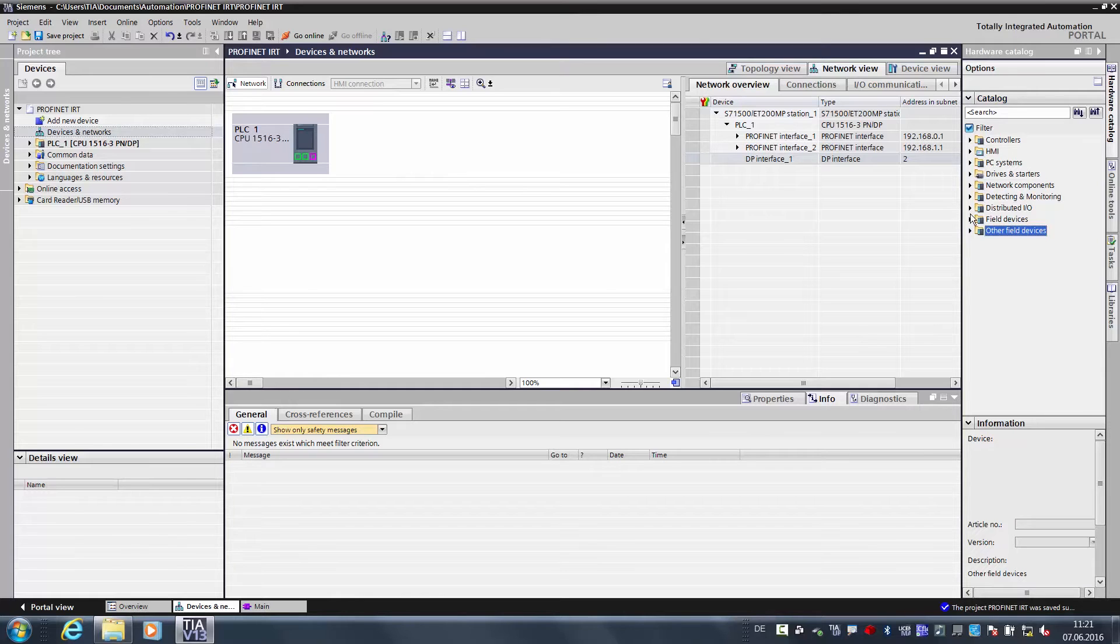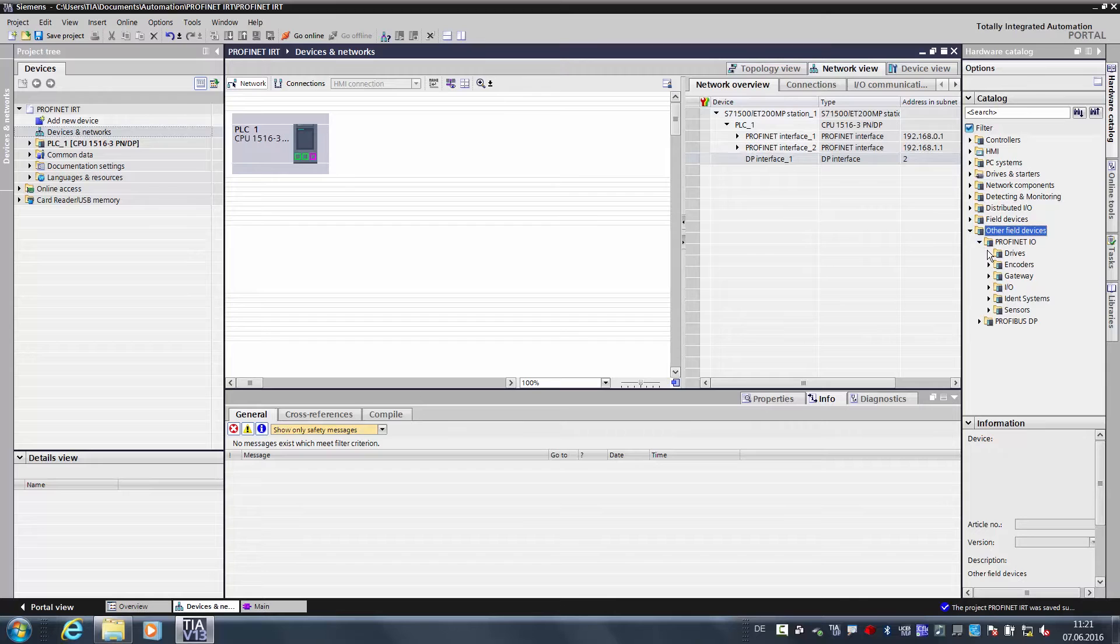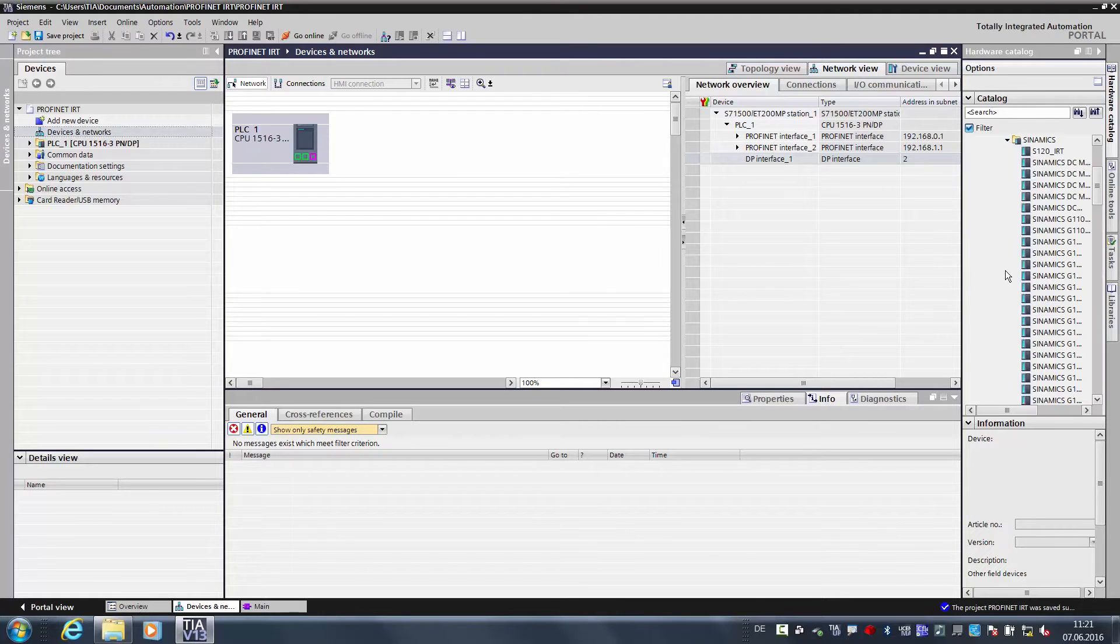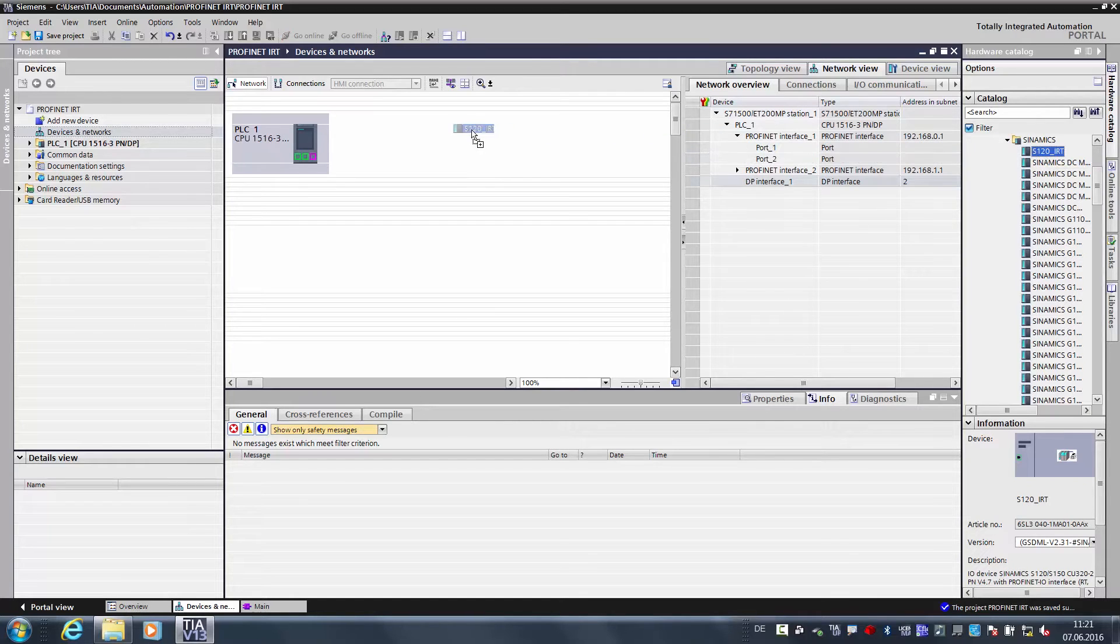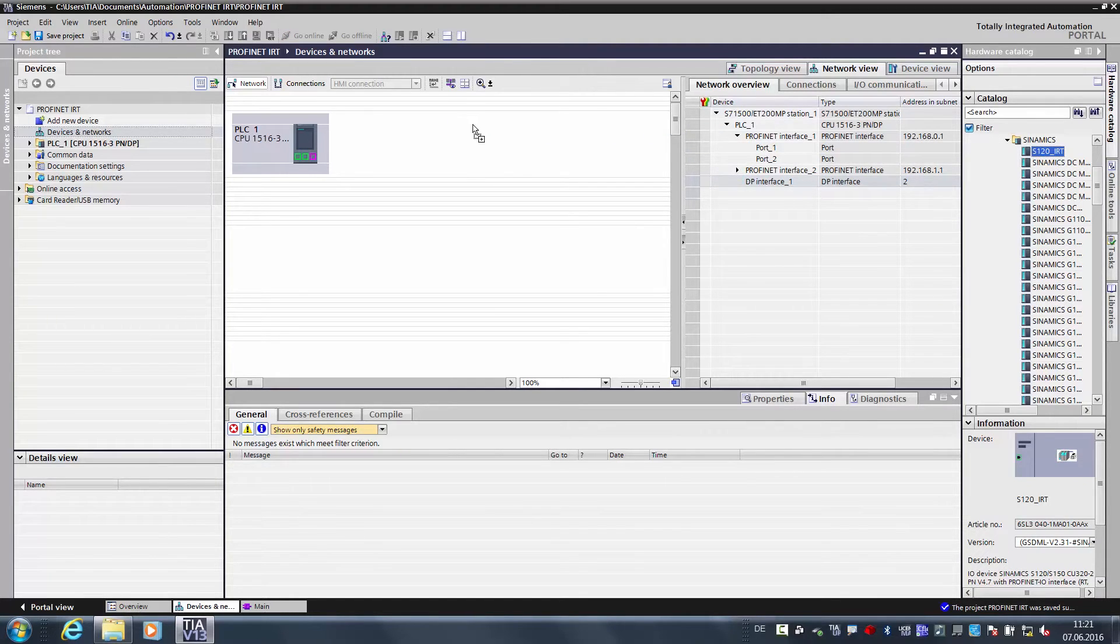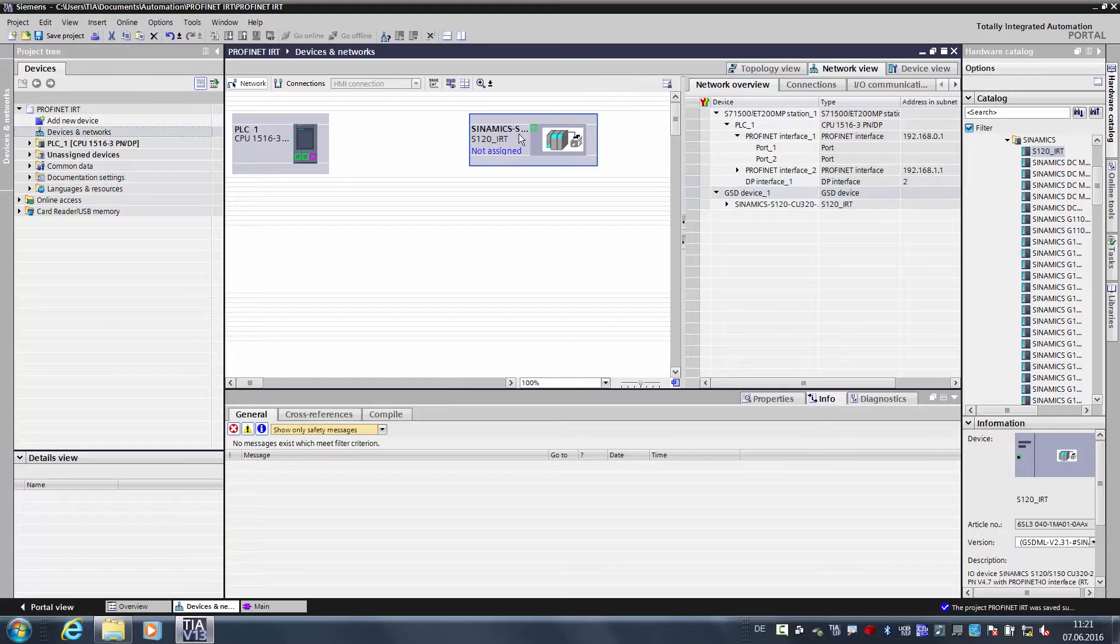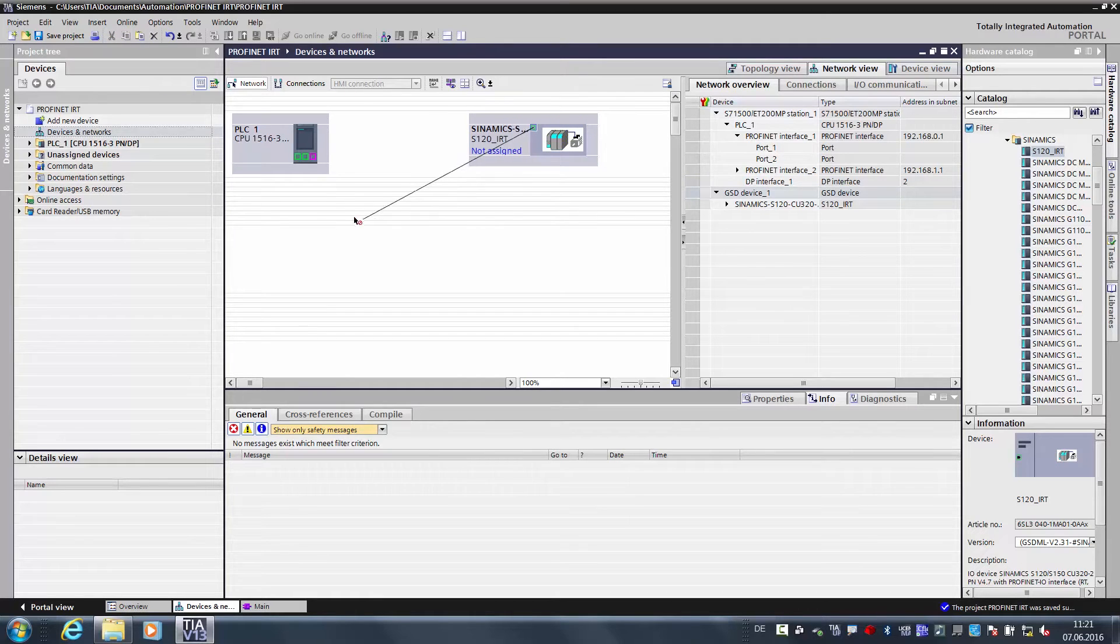Now I would like to integrate the drive into the project. To do so, I go into the hardware catalog, open the additional field devices, PROFINET IO, DRIVES, Siemens, SINAMICS, and SINAMICS S120 is the exported GSD file that I would now like to import. And I will now use drag and drop to connect the drive to the S7-1500.